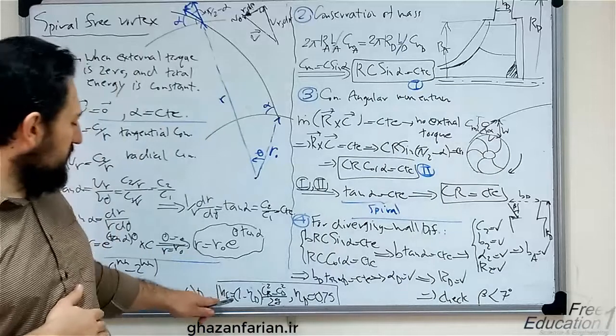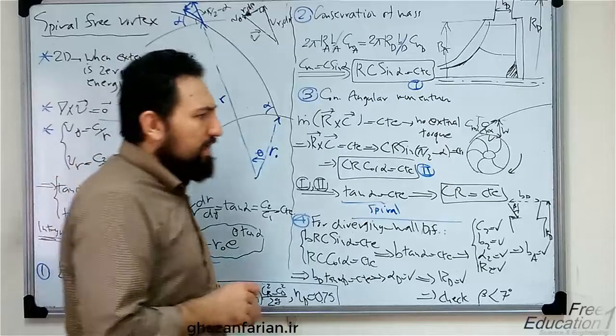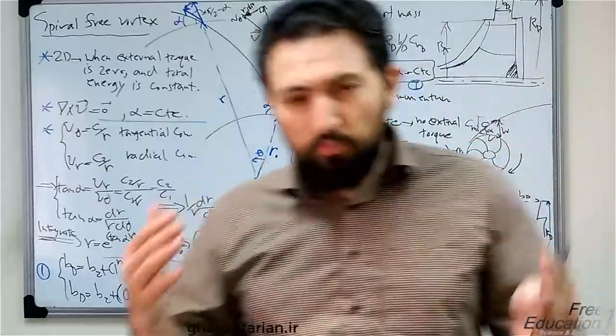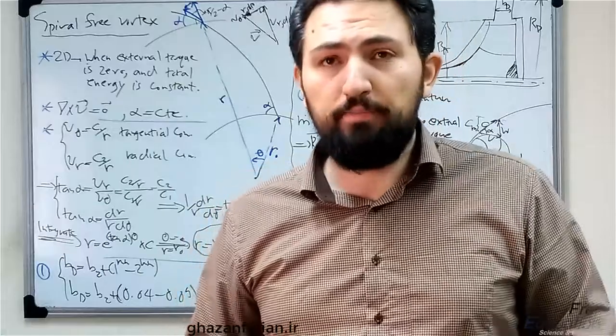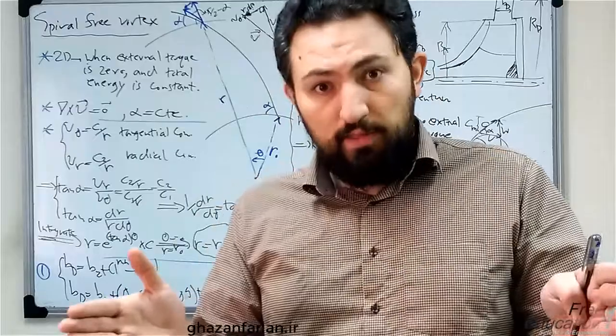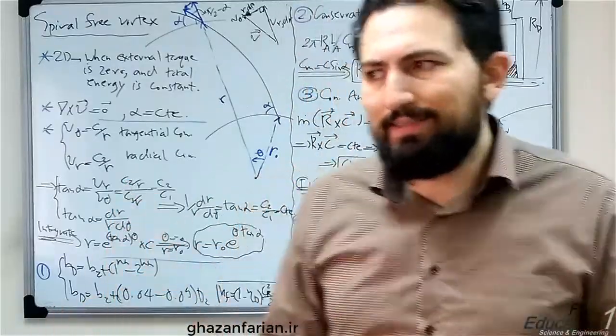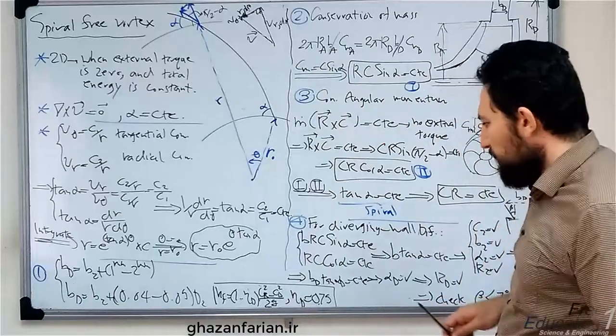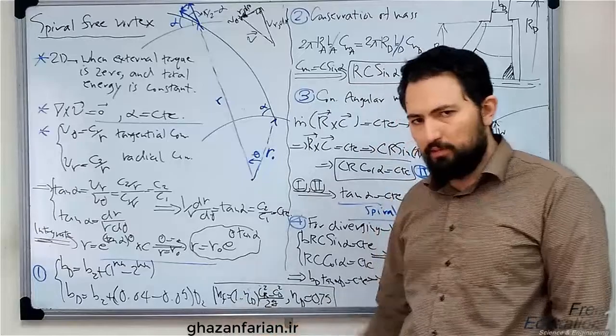The other point here is about the hydraulic losses or the efficiency of the diffuser. If you increase the load of the diffuser — meaning if you decide to decrease the velocity at the output down to one-third of the incoming velocity — there is a large velocity reduction, so the hydraulic losses greatly increase and the efficiency of the diffuser decreases. This is a relation for computing the hydraulic or frictional losses inside the diffuser.